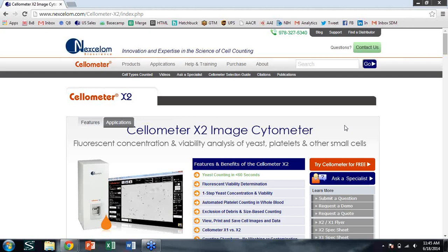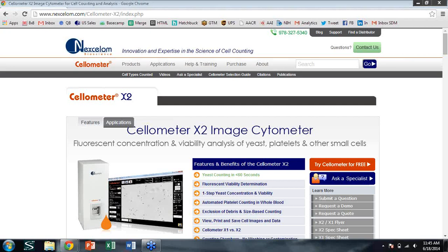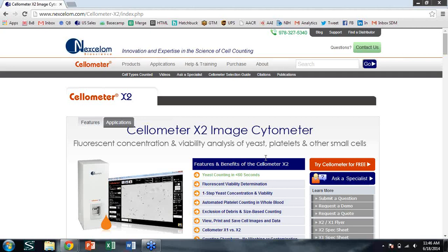A question from Jason: can the Cellometer T4 be used for the AO/PI counting method? The T4 is a bright field only counter with no fluorescence capability, so AO/PI counting is not possible. The T4 also has only 4× magnification, making it difficult to count yeast cells, which range from 4 to 10 microns — it is designed for larger cells such as cancer cells, stem cells, or other mammalian cells. The Cellometer X2 is needed for yeast AO/PI fluorescence counting.